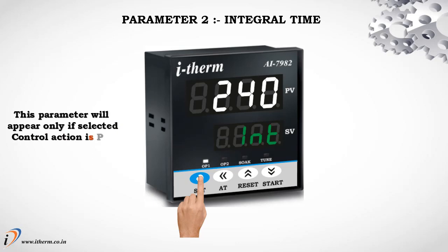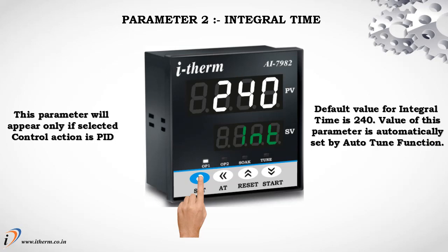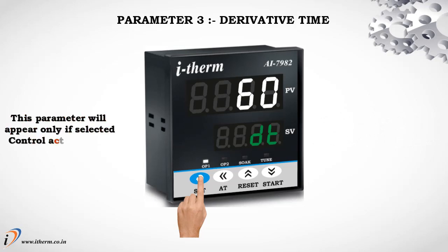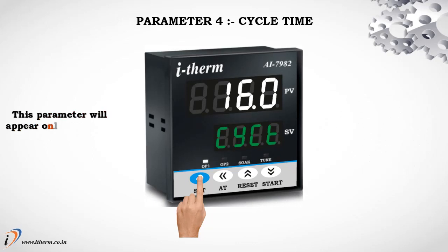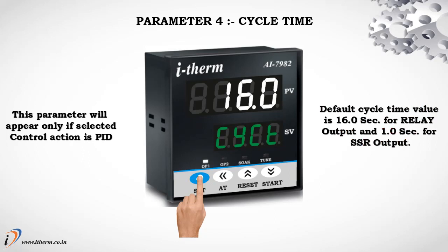Parameter 2: Integral time. This parameter will appear only if selected control action is PID. Default value for integral time is 240; value is automatically set by auto-tune function. Parameter 3: Derivative time. This parameter will appear only if selected control action is PID. Default value for derivative time is 60; if set to 0, this function will be disabled. Value is automatically set by auto-tune function. Parameter 4: Cycle time. This parameter will appear only if selected control action is PID. Default cycle time value is 16.0 seconds for relay output and 1.0 second for SSR output.